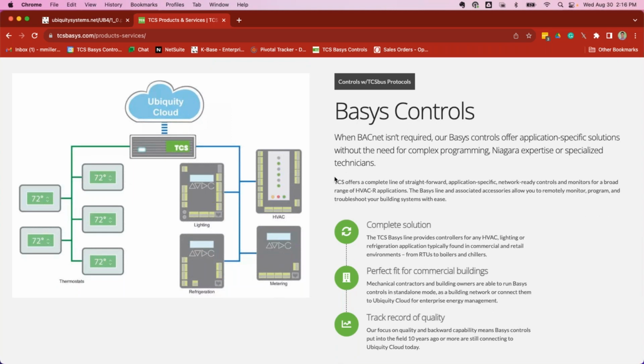As it was introduced by Sarah, we certainly do the room controllers, but we also have system controllers, including things like an air handling unit for a VAV application, or an air handling unit for a makeup air application. We also do chiller and boiler controllers, staging the boilers, bringing in your hot water supply and return temperatures, doing pumping controls and alternating them. Same thing with the chillers.